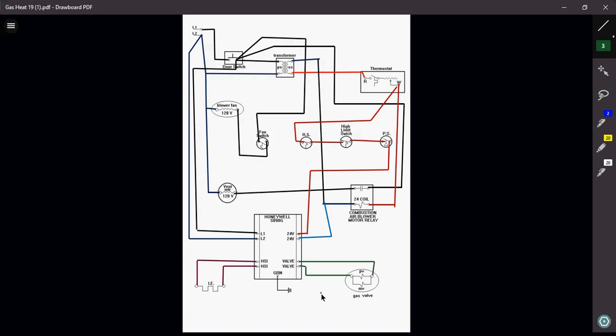After a couple of seconds, probably anywhere between 15 and sometimes 30 seconds, the gas valve will now open, and when that happens, the gas will make contact with that hot surface igniter, and it will ignite. Once the burners are lit, the furnace will begin to heat up. Once the furnace reaches somewhere around, again, probably about 140, maybe 150 degrees, my fan switch will now close, which will turn on our blower motor.